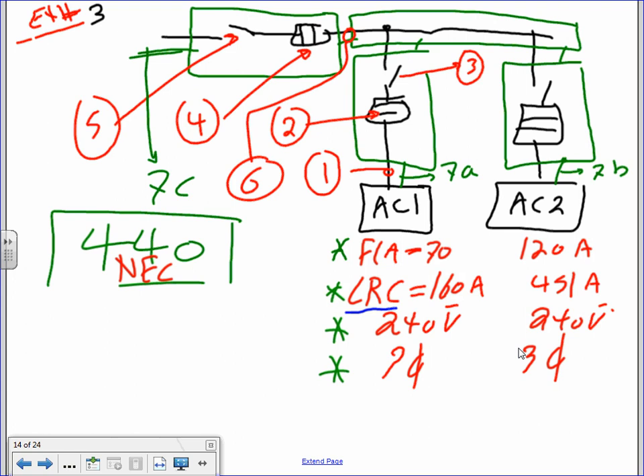The calculation is about 80% the same as what we're going to do, slightly different though. We have a feeder with a disconnect and a fuse coming to a gutter, and the gutters are feeding a combination fuse disconnect — no starter — and both of them are feeding AC units, a chiller, anything that cools the system.